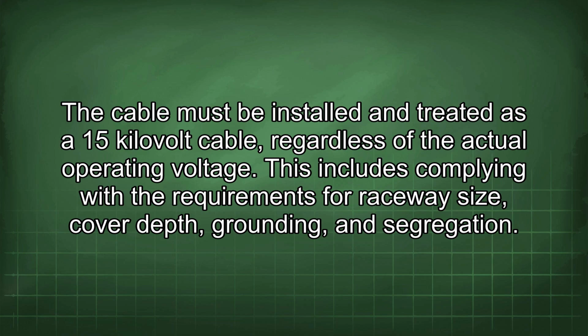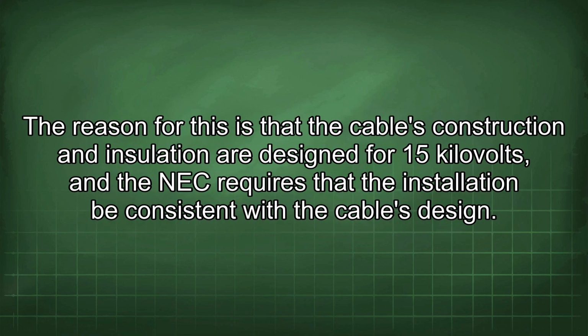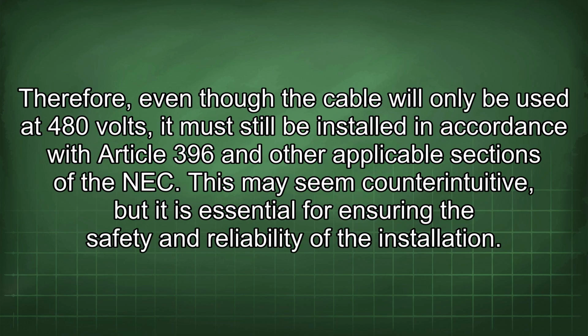This includes complying with the requirements for raceway size, cover depth, grounding, and segregation. The reason for this is that the cable's construction and insulation are designed for 15 kV, and the NEC requires that the installation be consistent with the cable's design. Therefore, even though the cable will only be used at 480 volts, it must still be installed in accordance with Article 396 and other applicable sections of the NEC.